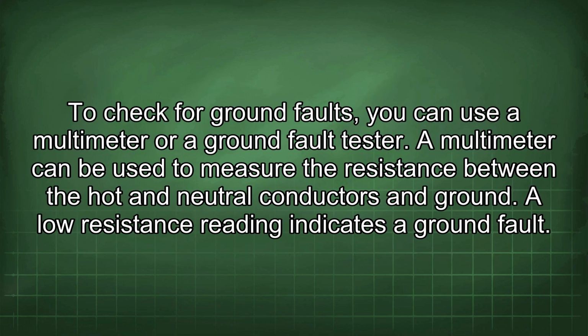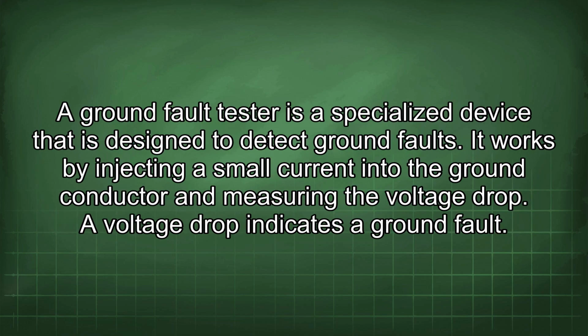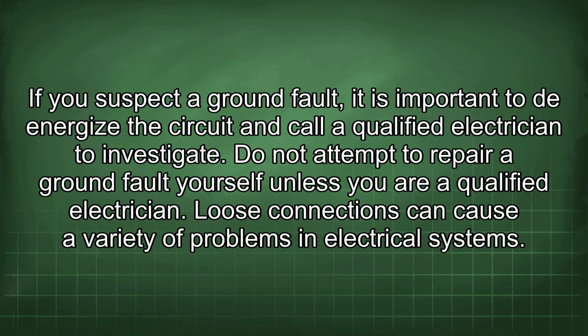To check for ground faults, you can use a multimeter or a ground fault tester. A multimeter can be used to measure the resistance between the hot and neutral conductors and ground. A low resistance reading indicates a ground fault. A ground fault tester is a specialized device that is designed to detect ground faults. It works by injecting a small current into the ground conductor and measuring the voltage drop. A voltage drop indicates a ground fault. If you suspect a ground fault, it is important to de-energize the circuit and call a qualified electrician to investigate. Do not attempt to repair a ground fault yourself unless you are a qualified electrician.